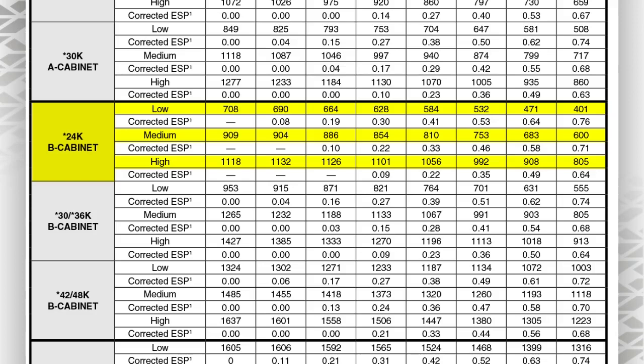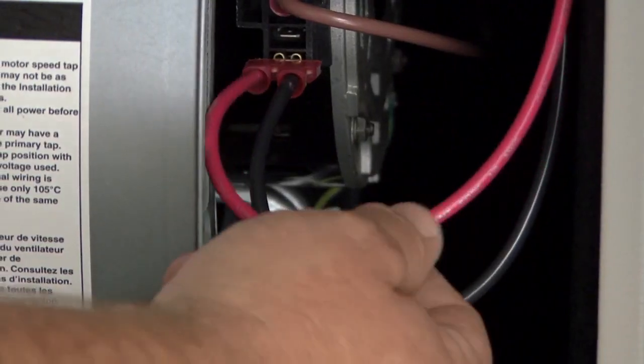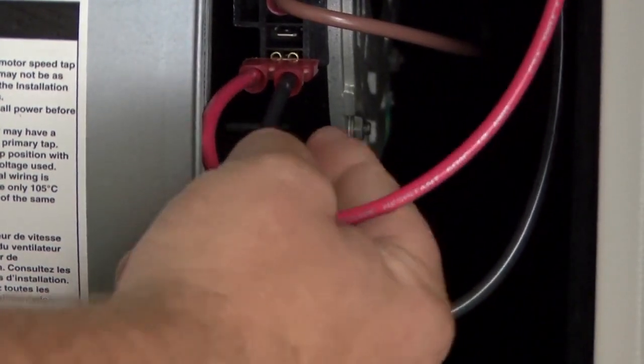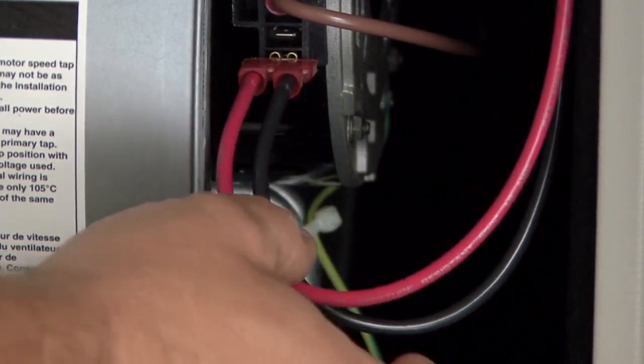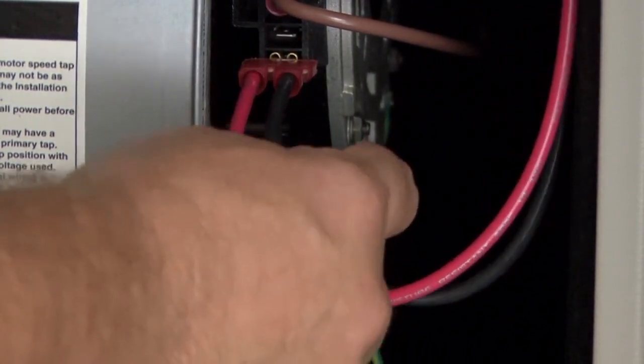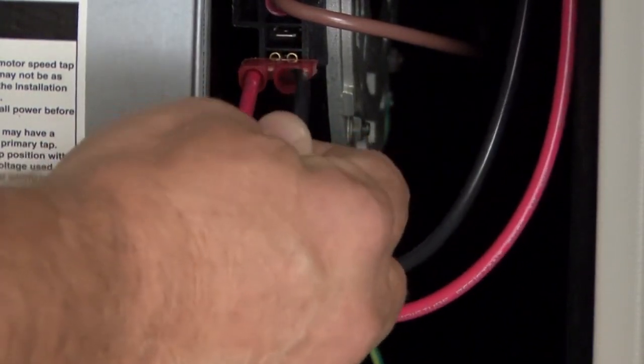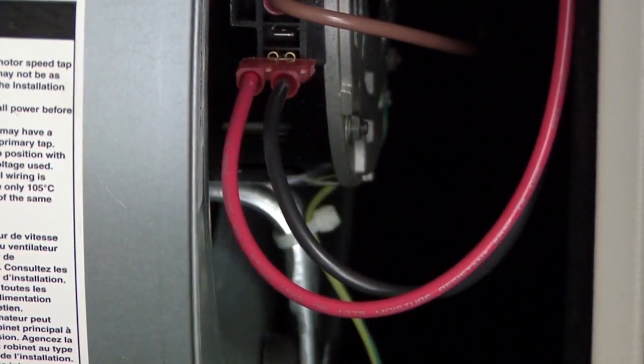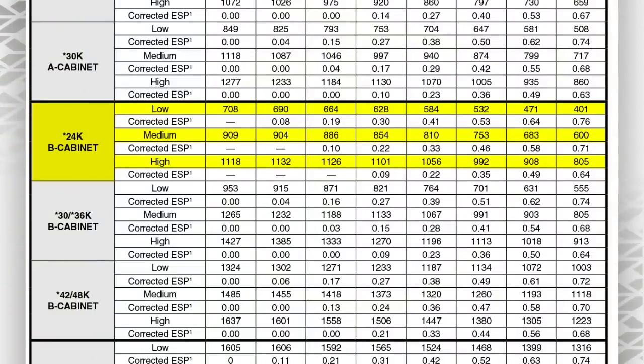Say you only had a 5 kW, low speed should be adequate for a 5 kW. So you could leave the red wire going to terminal number 6 on that motor, and let's say we needed to go to terminal 5, which would be medium speed on the blower motor. We could put that on terminal 5 and separate the two speeds. So when it's in electric only, it would be energizing the red wire and bringing on the electric heat. And if it was heat pump, it would be at medium speed.